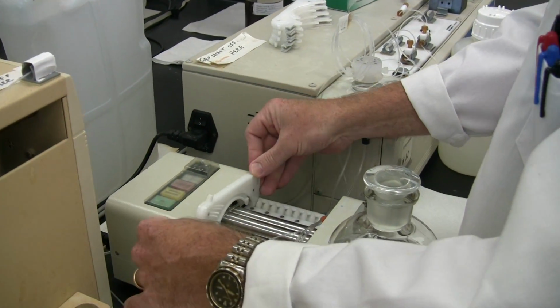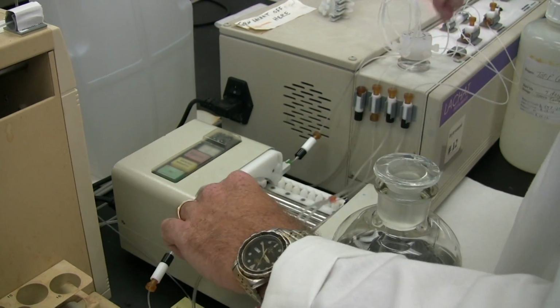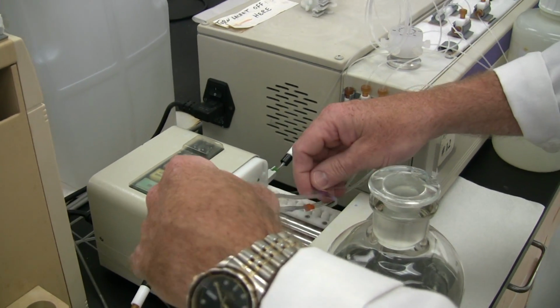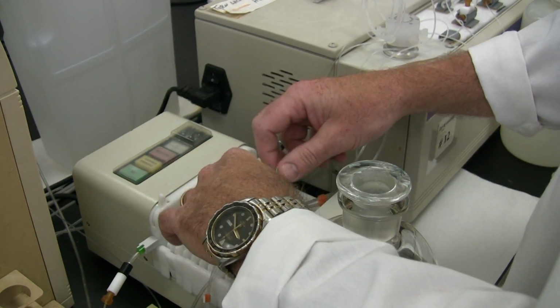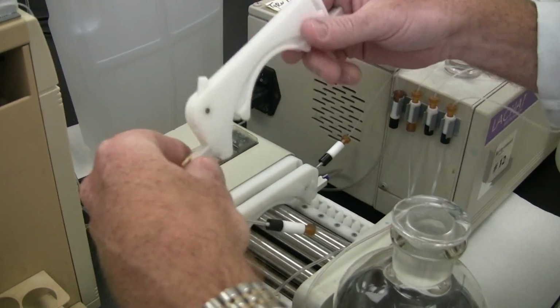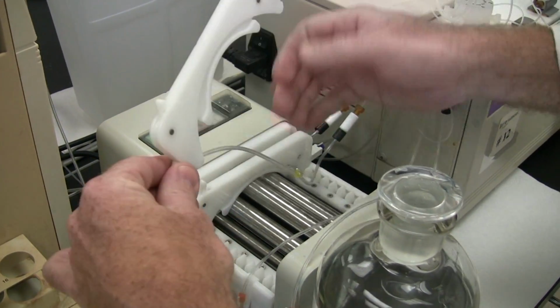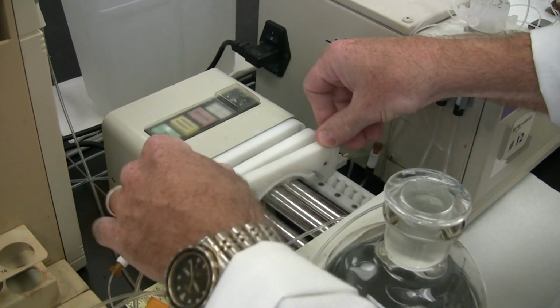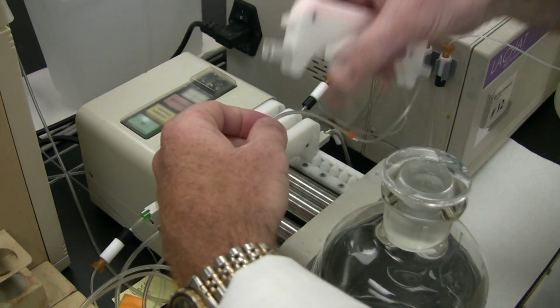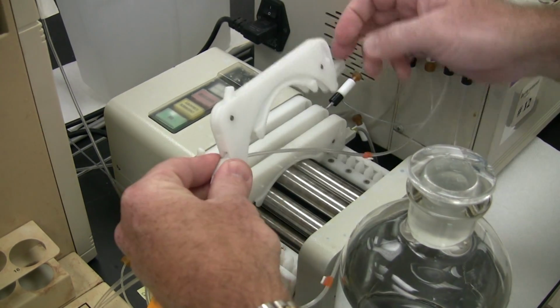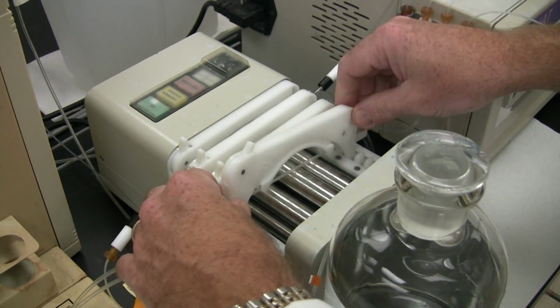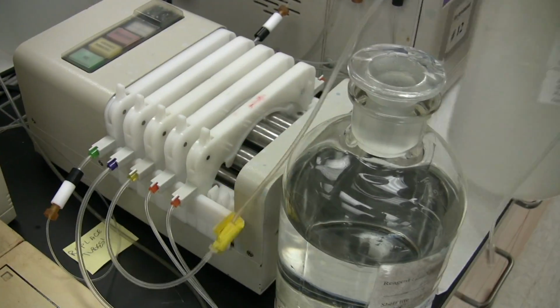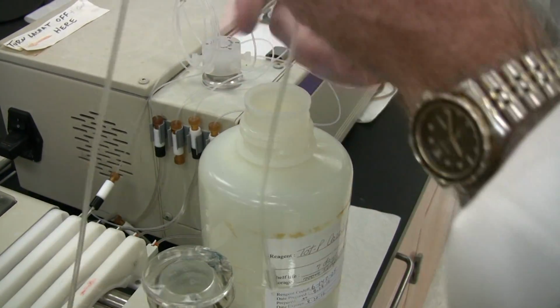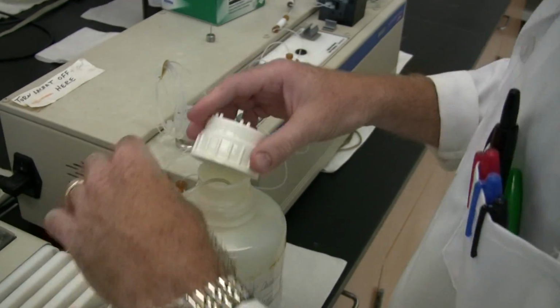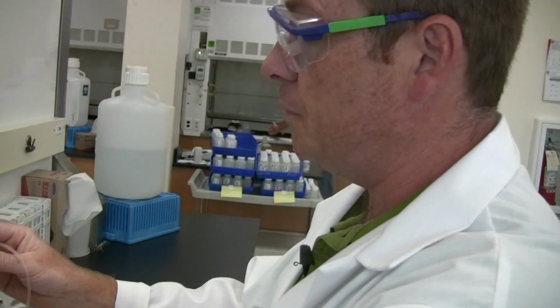This is a peristaltic pump and has rollers that through peristalsis will move the reagents into the instrument, and what will be going in here is water, a color reagent, and then a carrier is what's going into this manifold. The pump tubes are different diameters to proportion things correctly. So right here is an acidified carrier that matches how much the samples are acidified. This is going to an ascorbic acid reagent, which is part of the color reagent.